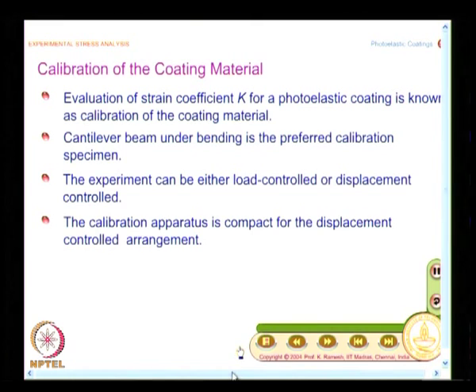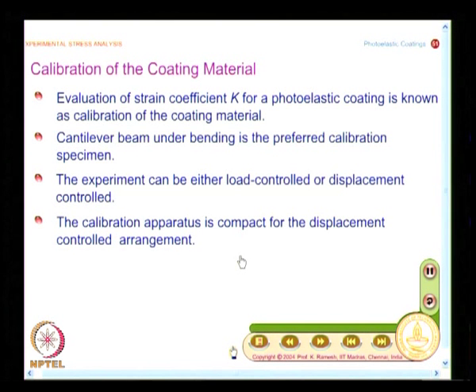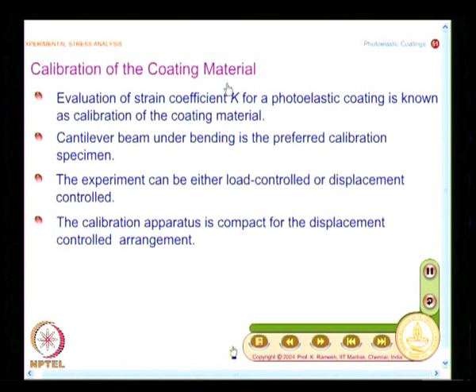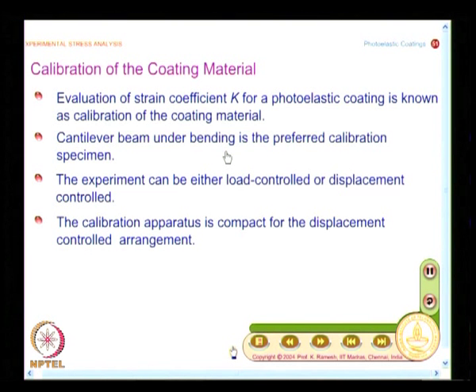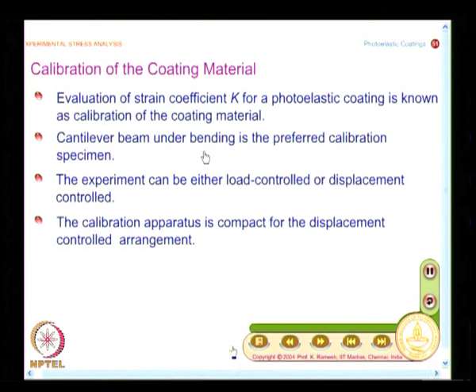We now move on to an important aspect of a photoelastic coating test: how to calibrate the coating material. The meaning of calibration is the evaluation of the strain coefficient K for a photoelastic coating. The most preferred calibration specimen is a cantilever beam under bending. Later we are also going to study brittle coatings followed by strain gauges.